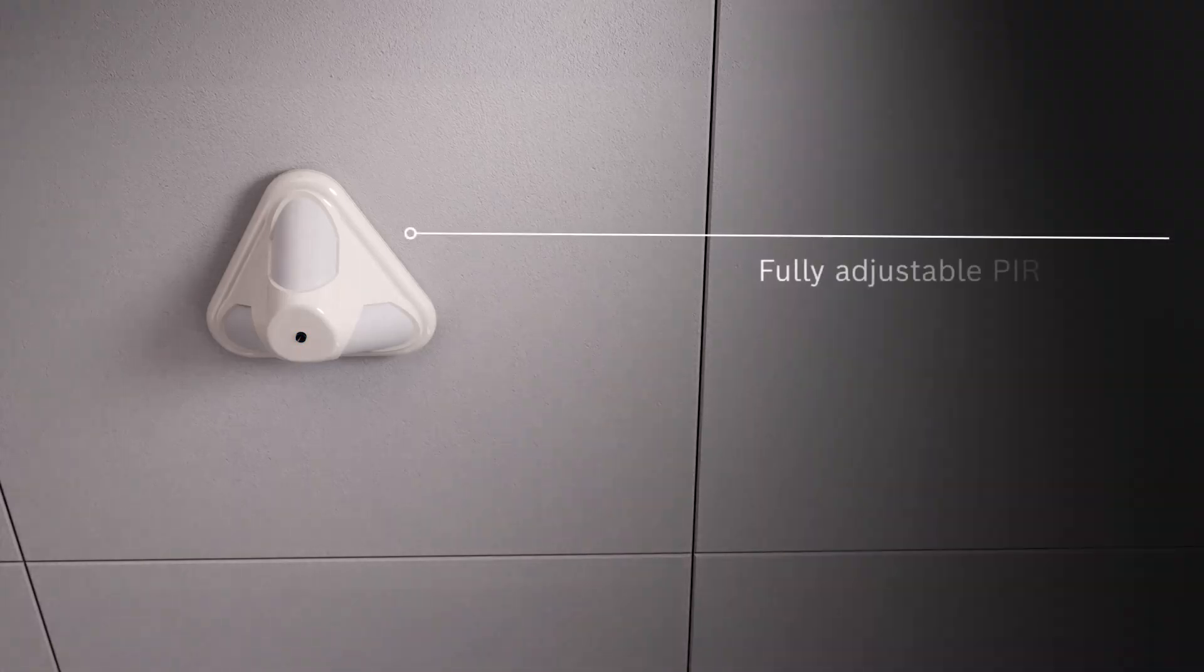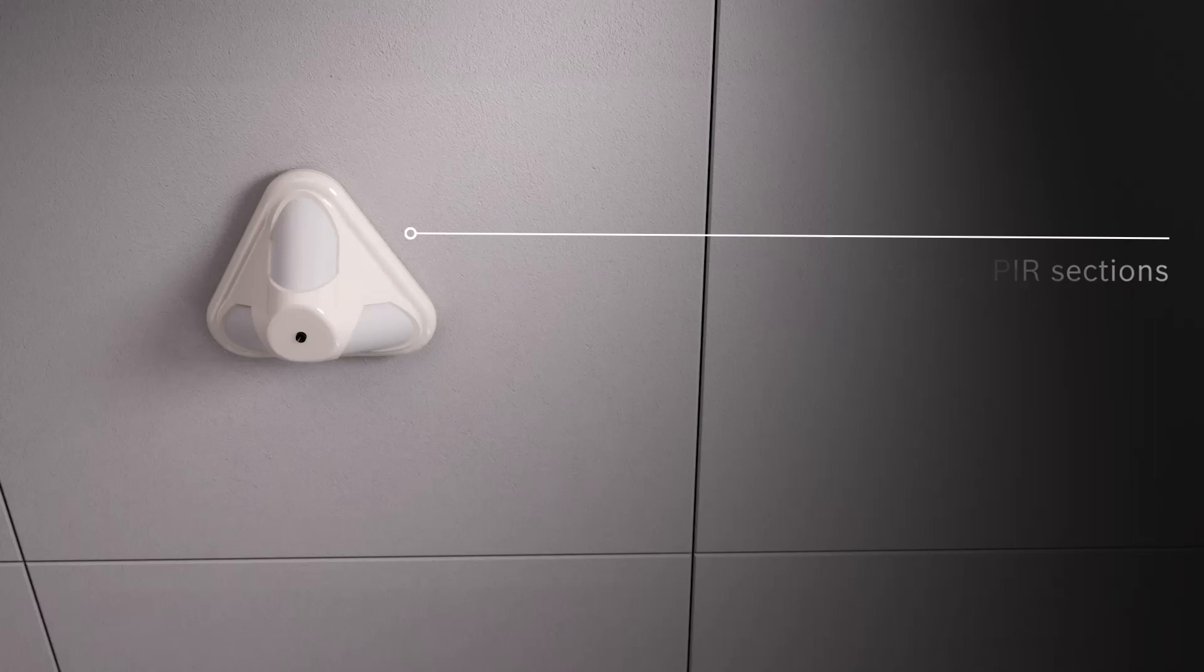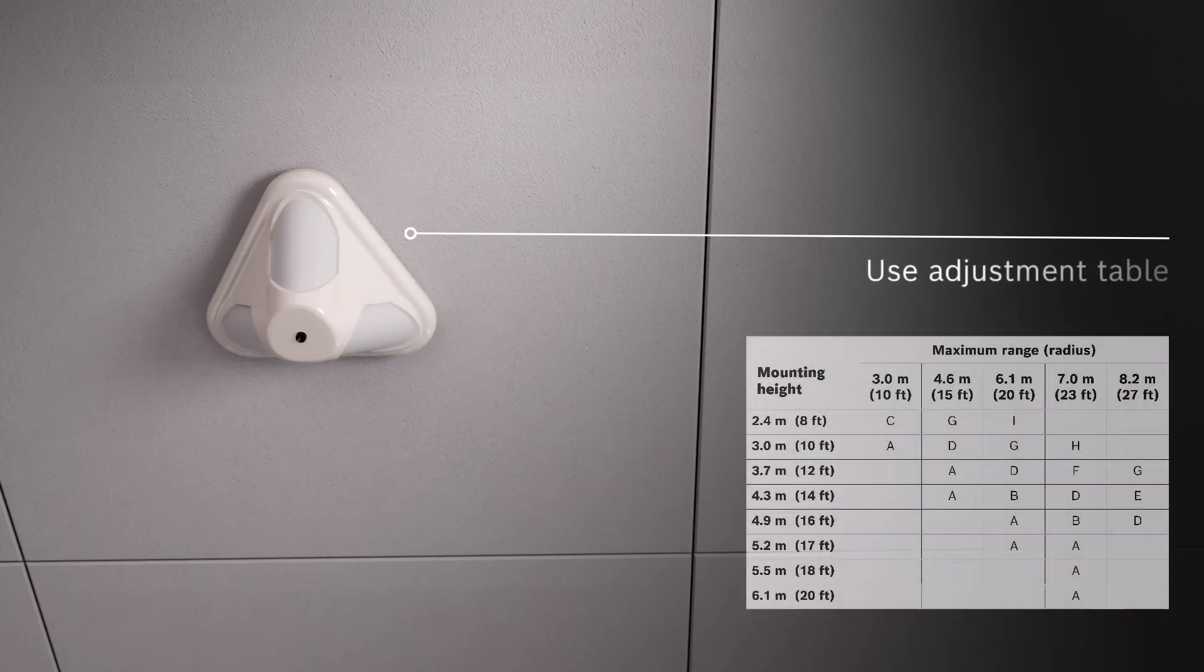In summary, ceiling mount motion detectors have three separate PIR sections that are fully adjustable. The maximum range of the detector depends on the mounting height and the vertical adjustment of the lens. Use the optical module adjustment table to adjust each PIR section.